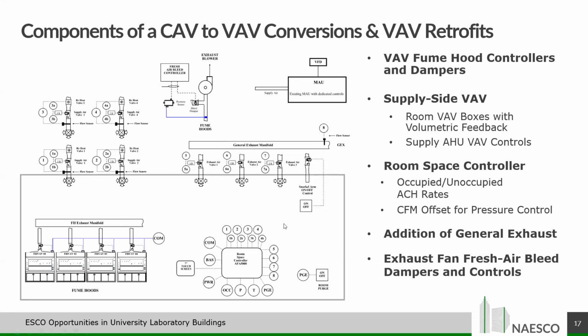Now, that's what you're doing in the labs. You also have to make sure that your exhaust fan is VAV. So sometimes you need to add a fresh air bleed damper and control that to maintain a constant static pressure in your exhaust plenum. We're going to discuss this a little bit later. And then on the supply side, your makeup air unit needs to have a VFD and a static pressure controller, again, so you're just maintaining constant static pressure in this supply air system.